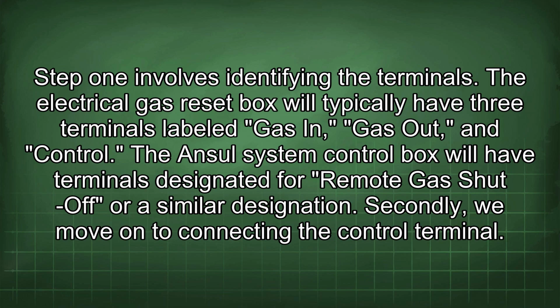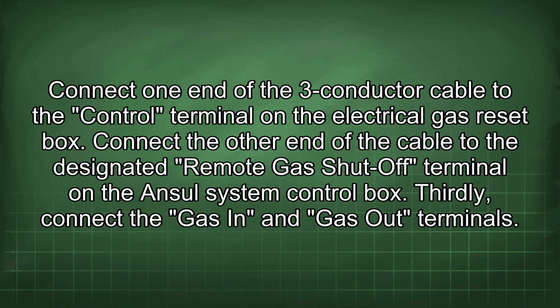Secondly, we move on to connecting the control terminal. Connect one end of the 3-conductor cable to the control terminal on the electrical gas reset box. Connect the other end of the cable to the designated remote gas shut-off terminal on the Ansul system control box.